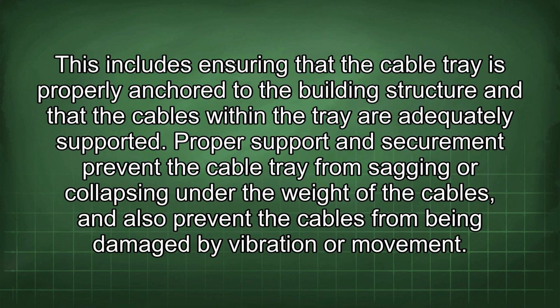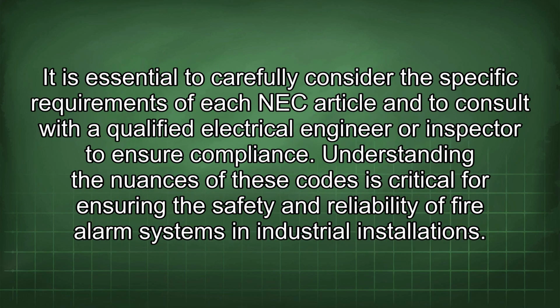This includes ensuring that the cable tray is properly anchored to the building structure and that the cables within the tray are adequately supported. Proper support and securement prevent the cable tray from sagging or collapsing under the weight of the cables, and also prevent the cables from being damaged by vibration or movement. It is essential to carefully consider the specific requirements of each NEC article and to consult with a qualified electrical engineer or inspector to ensure compliance.